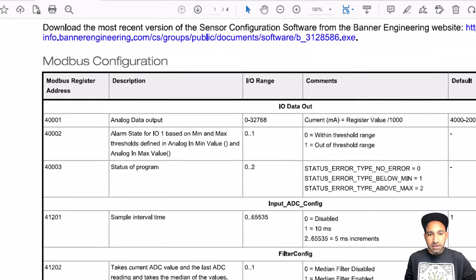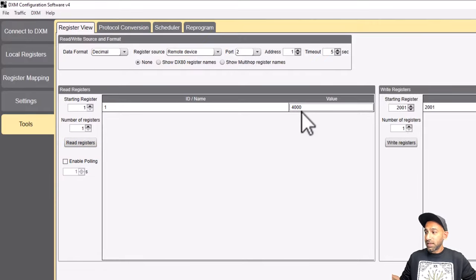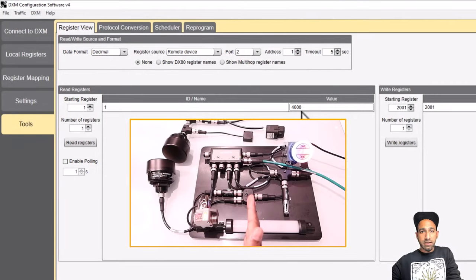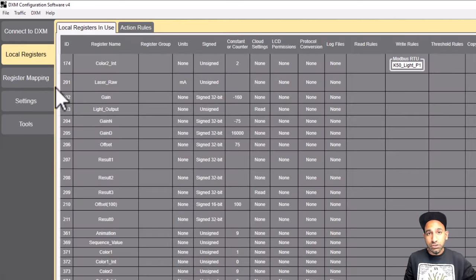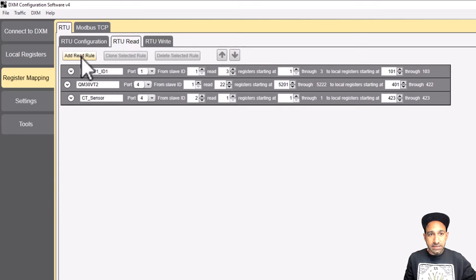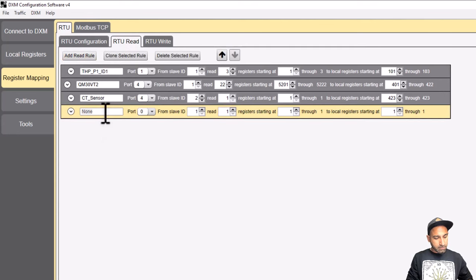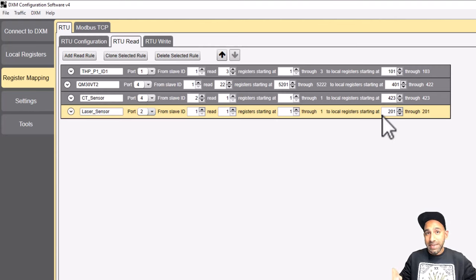If I read register one, I see it's showing 4000, which means no value. If I put my hand in front of the sensor and read again, the value changes — I'm getting values from 4000 to 20,000 as a raw value. Now I need to store this value into the controller. I can add an RTU read command — name it 'laser sensor', port two, slave ID one, read one register starting at one — and store the result in register 201, which is the register in my controller.